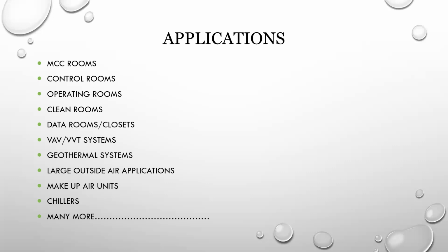A lot of times they throw an air conditioning unit into a data room, and it's not designed to do any dehumidification. VAV and VVT systems. Thing about that is as the VAVs close off and you reduce the airflow, if you don't have something taking care of the capacity on the unit, you have issues. Geothermals. They are designed for loads in the north for the heating loads. When they go on the cooling load, they're extremely oversized. Large outside air applications, normally up to 60%. After that, you've got to have some kind of reheat. Also make up air units, chillers, many more.